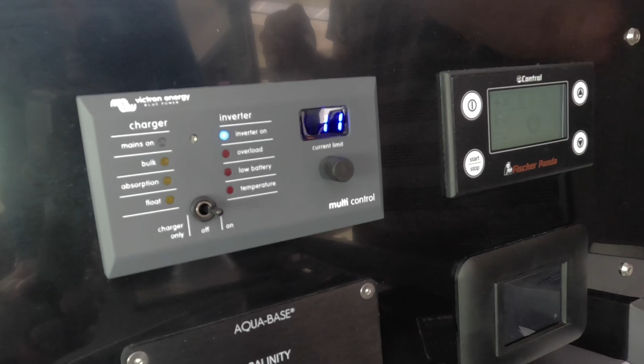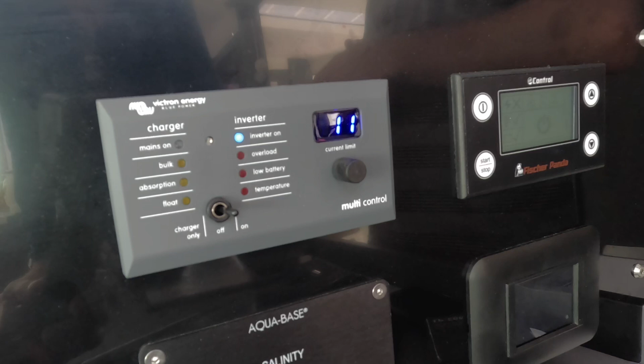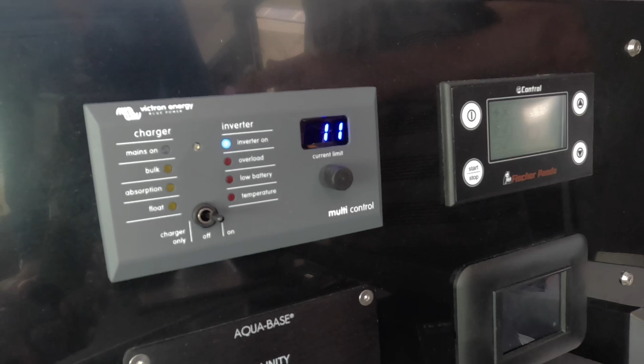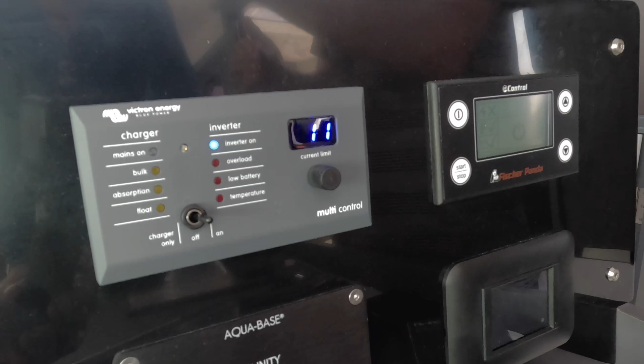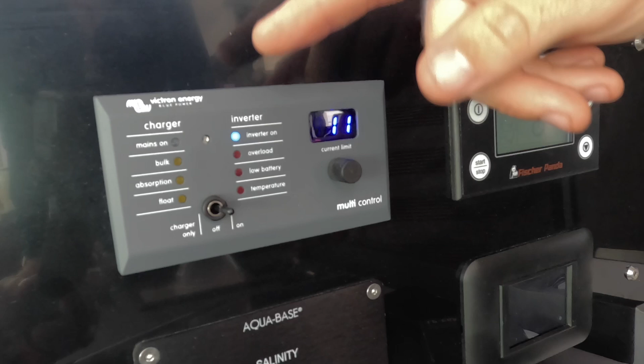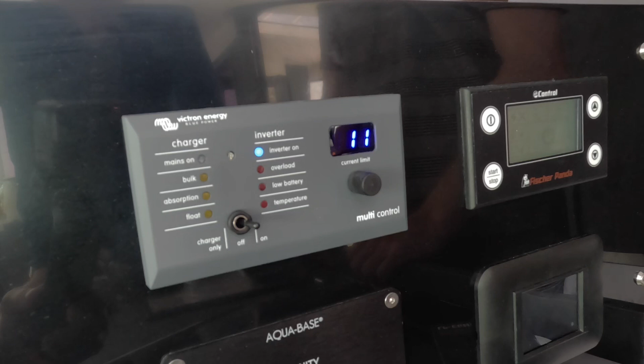For example, that's the charger of the 48 volt battery. If you're at the dock and the 48 volts is like 20%, you charge at the dock, it will go in bulk, so it will go full charge at 3-4 kilo, and at 80-85% it will go through absorption and reduce the level of charging to 1 or 2 kilo, and it will reduce until the floating tension, which for the 48 volts is around 56-57 volts, and at the floating tension it will stop and remain on floating.